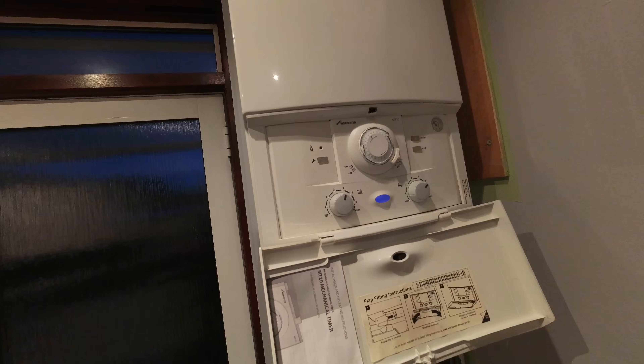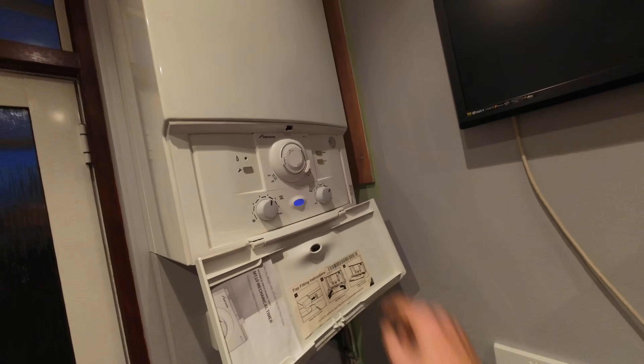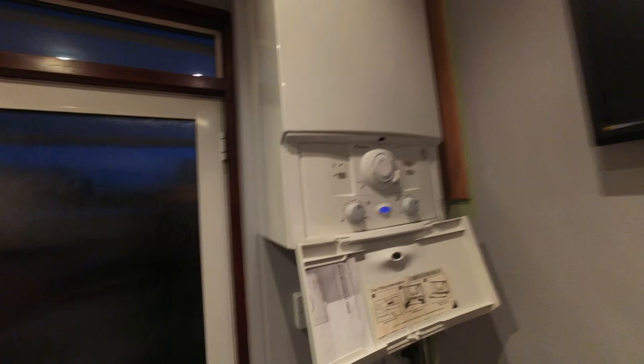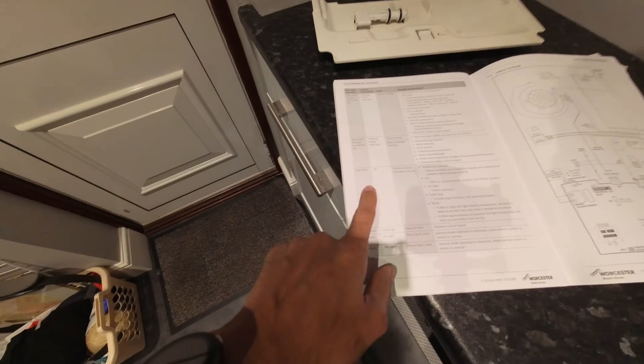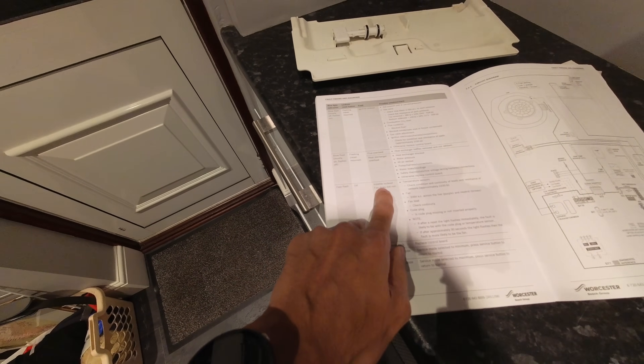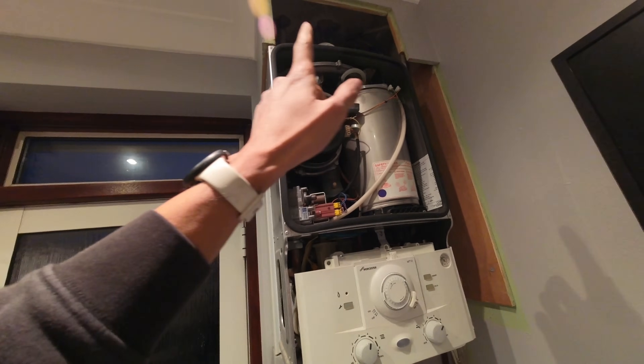Got a Worcester Greenstar 30SI — customers have been away, come back, and it's not doing anything. The diverter's moved over, I can hear that, pump's running. I reckon the fan's gone again on this one — similar scenario, they've been away for a while and come back. I'll wait to see what sequence of flashing lights we get, but in the meantime I'll get the case off and do some tests on the fan. We've got a fast flash on the blue light — looking in the MIs for the fault-finding side, fast flash, lockout, volatile lockout, fan doesn't run.